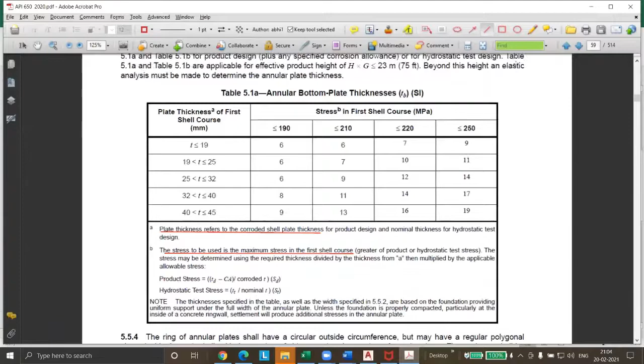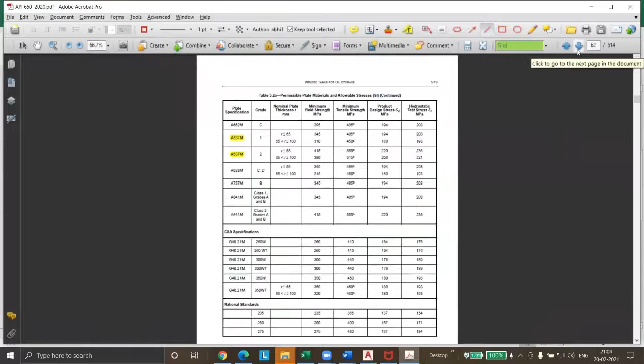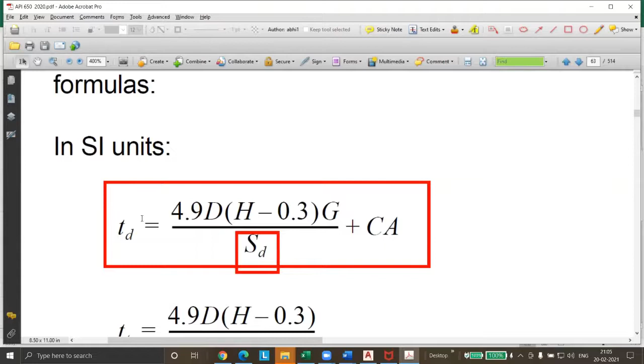The thickness is now known. So can we calculate the stress? Yes. Is it clear what I'm saying? As per thickness, we have to calculate the stress. Earlier we used the product stress and calculated the thickness. The SD was known based on the material. Now TD is known and we are calculating this SD, the stress in that shell course. All the other factors will be the same. So we can calculate TD, and we can also calculate TT. For this TT, we'll have the nominal thickness and we can calculate the SD, right?